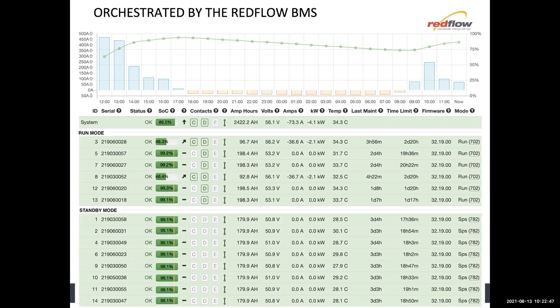So what's going on here is you've got 60 kilowatt hours of operating energy that acts just like any other battery, charging and discharging. This site has solar on it, and if there's enough solar, the 6 batteries are enough to keep the site running overnight. When you've got bad weather, a bad solar day or a few days in a row, the battery management system simply wakes up the standby batteries as required, in sequence, in the number of units needed at each time, deploying them like 8 little miniature gensets that fire up on demand to add more energy to get you through the night.